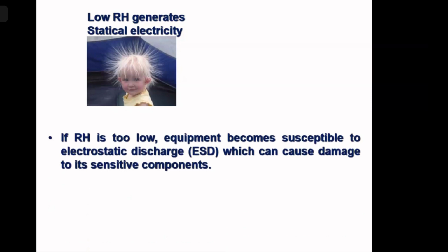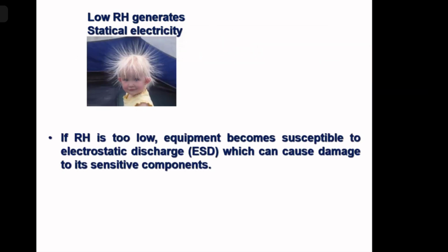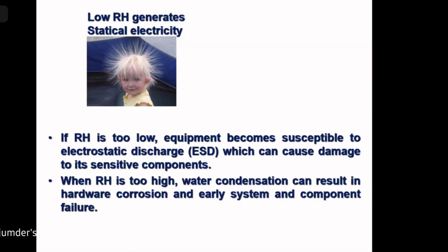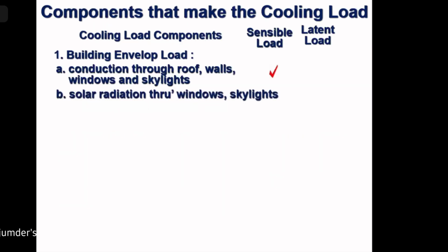So, the intermediate area is between 40 and 60%. So we should try to keep RH of electrical load between 40 and 60%. You see the gap there. Next. Generally, RH is kept between 40 and 60% with alarm provision when the RH goes below 30% or goes above 70%. Next.